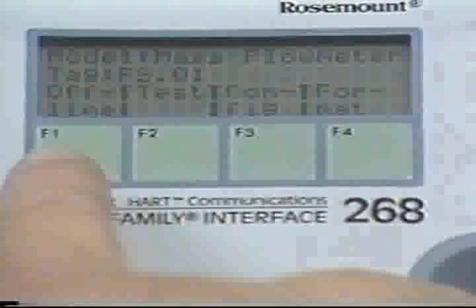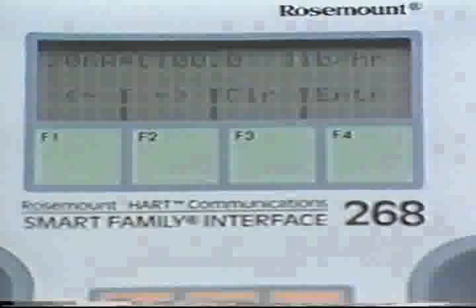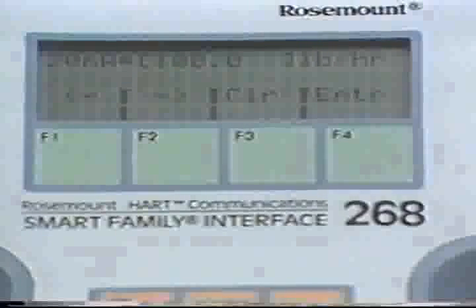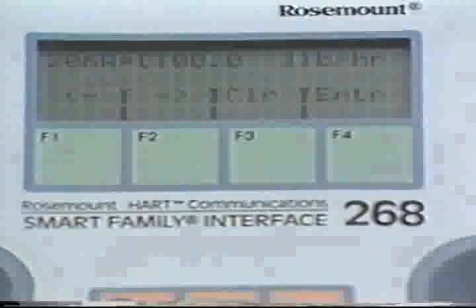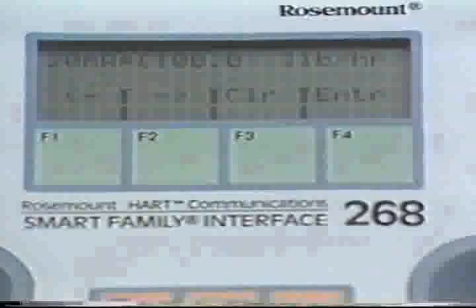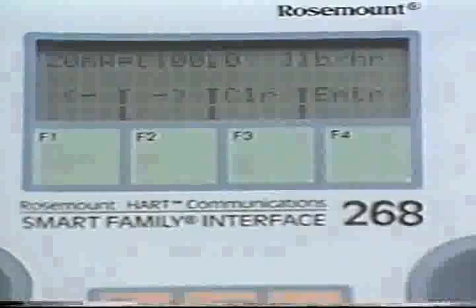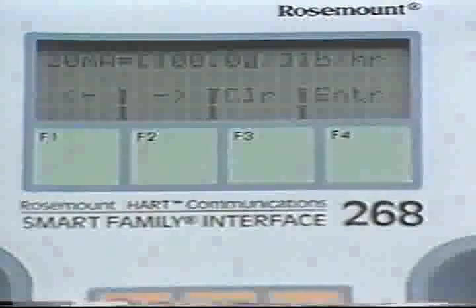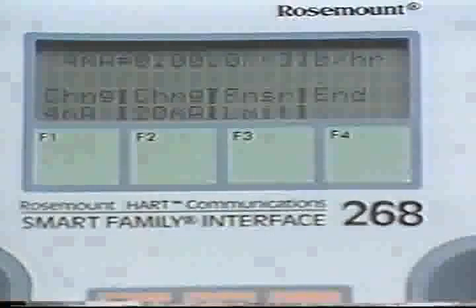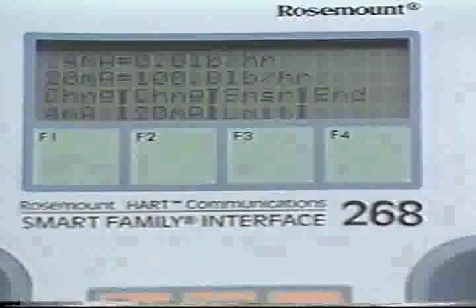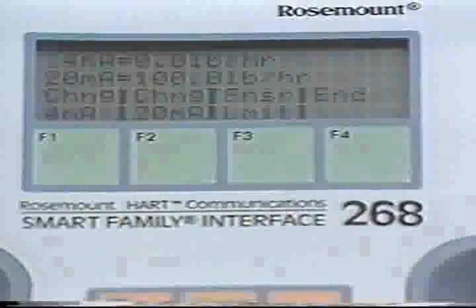Before we configure the smart mass flow meter, let's take a closer look at the interface device. The configuration information is displayed on a liquid crystal display. The top two lines of the LCD display user prompts and the values entered by the user. The bottom two lines of the LCD display labels for the function keys, F1 through F4. The bottom two lines can also display a current list of choices available to the user. When the device is turned on, a self-diagnostic program is initiated. This ensures that the interface is operating and communicating properly with the transmitter.